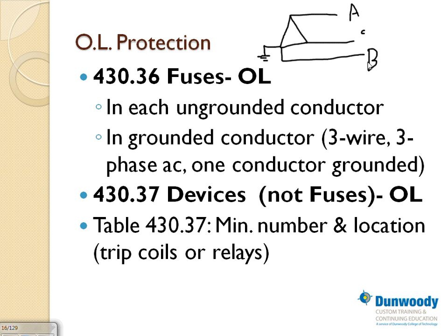But if you were to use a fuse as an overload protection device, then you have to put the fuse here. By the way, if you're not using the fuse as an overload protection device, you do not need to put a fuse in a grounded conductor. You don't have to. So if I have my own electronic trip overload, I only need 2 fuses for this system, one for A and one for C, and instead of a fuse on B, they put a copper connector, just a piece of copper to tie it. It's a grounded conductor, unless you're using it for an overload.